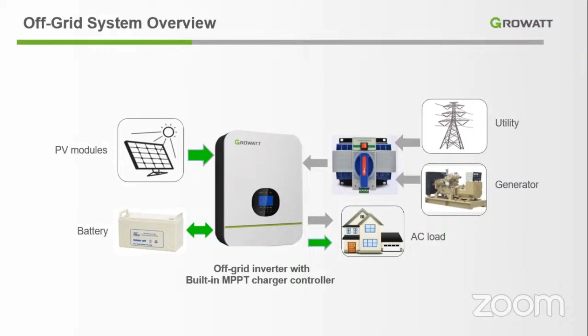Now, the first model that we are going to explain is the SPF 3000 LVM. This model is the white one, and we can connect it with batteries and PV modules. Take into account that it's mandatory to have a battery connected to this inverter. If not, it's not going to turn on. With this inverter, we can have a power factor of 1. It has an MPPT solar charge controller. It can be connected to Wi-Fi, but the Wi-Fi stick doesn't come in the same box. You have to buy it separately. So this is our first model.